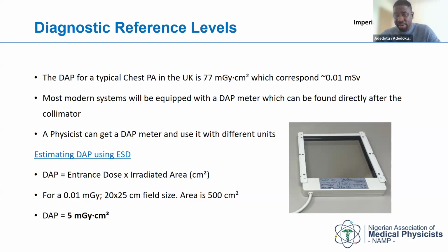If you know the irradiated area, if you can tell what the field size for your exposure is, then from the tube output, which you must have calculated during your QC, you can work out the entrance skin dose for a typical size patient. You can use a phantom for that. If you don't have that, you might have to use a TLD or an ionization chamber on the patient, which might be a bit discomforting for the patient. One of the easiest things for us to measure as physicists is the tube output.